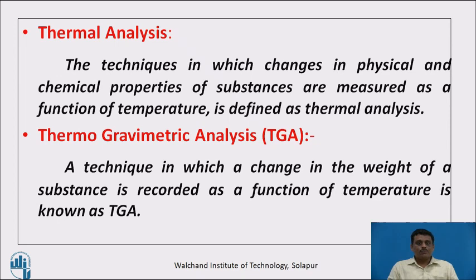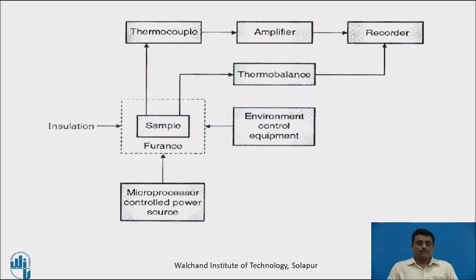In thermal analysis, we study what kind of changes occur in physical and chemical properties of substances with respect to heating of the sample. Now, this is the block diagram. The first part is a sample holder, where we hold a very small quantity of the sample to be analyzed. The sample holder is covered with a proper insulating chamber and is kept in a furnace.